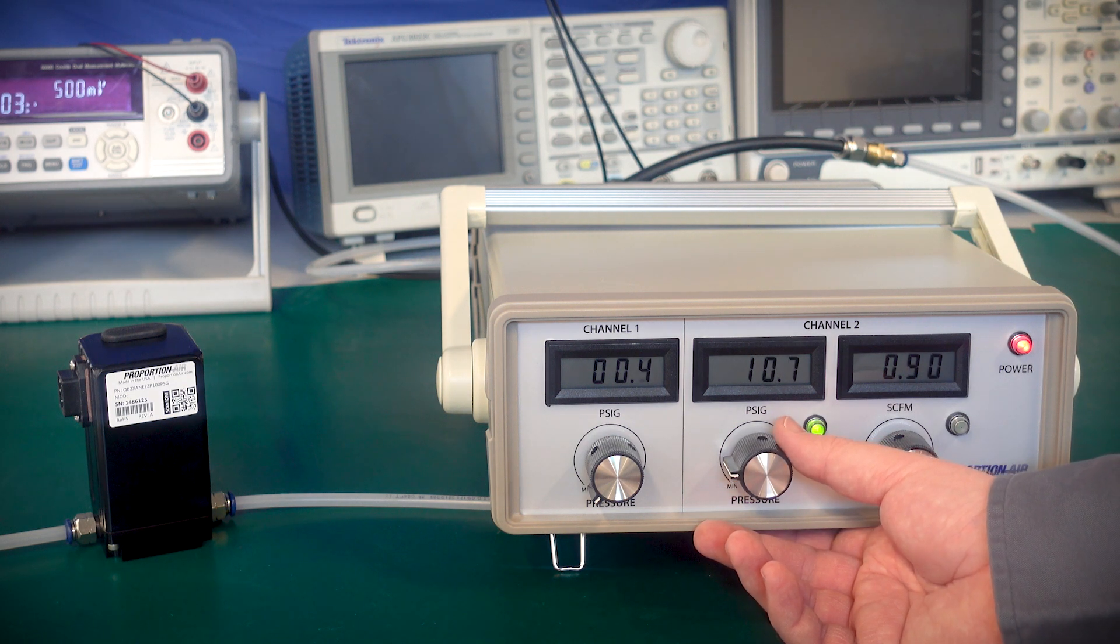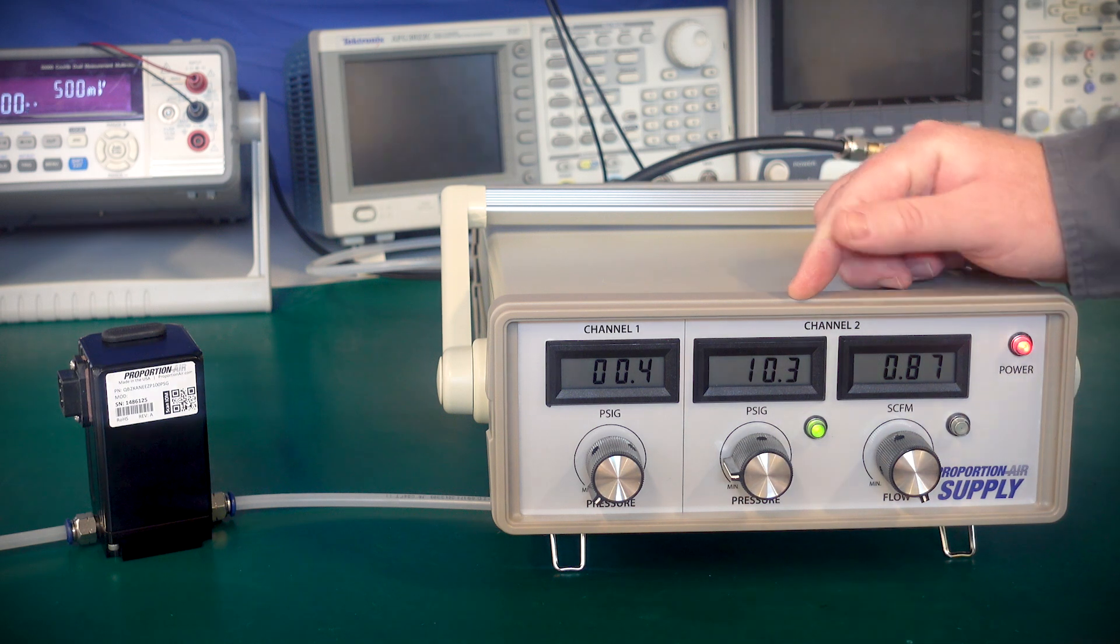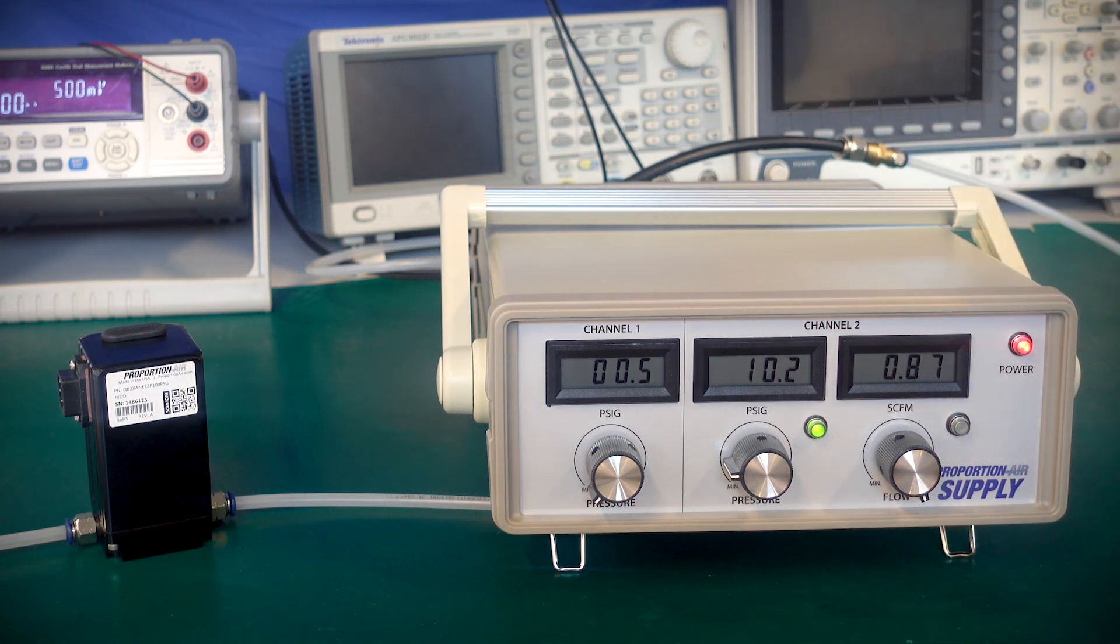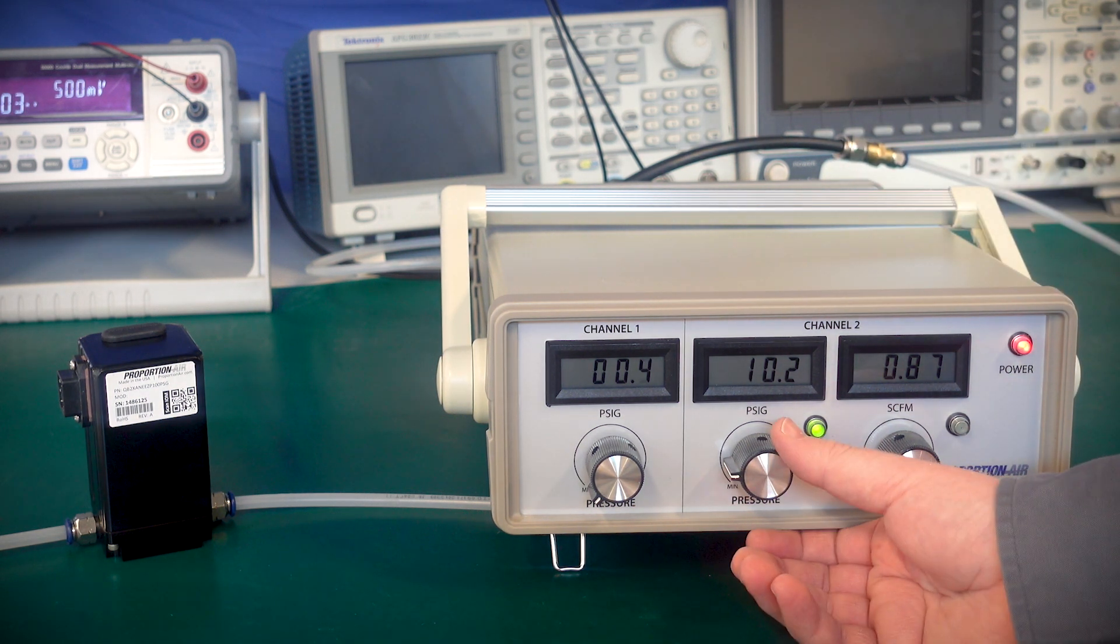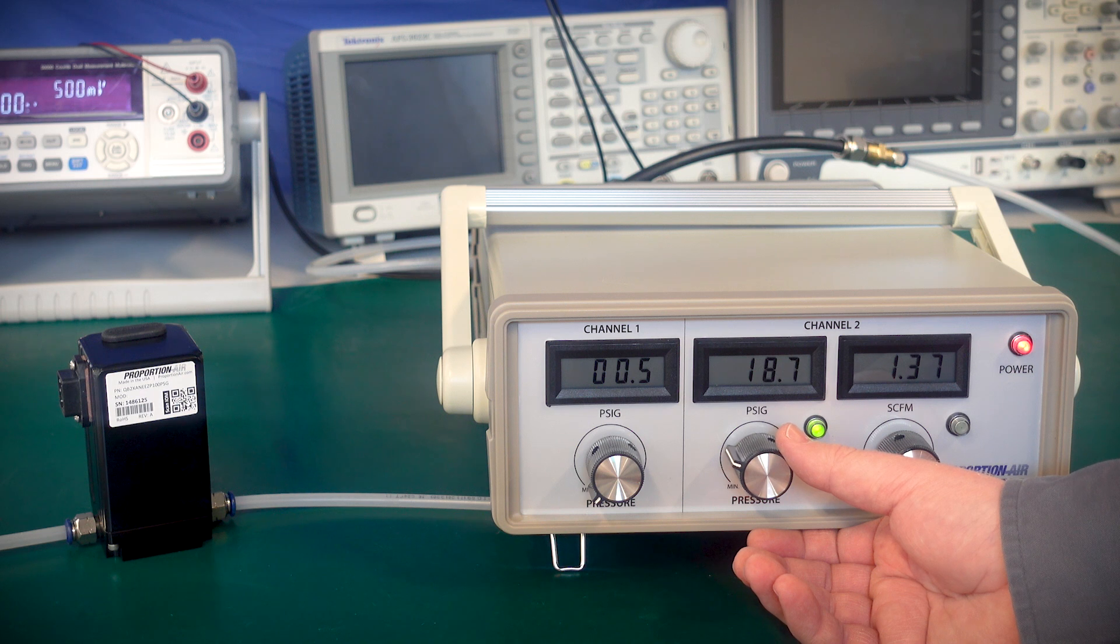To do so, we will turn the flow up to maximum so it is not limiting, and we will adjust the pressure. As we get to a set point, we will read the flow. We will adjust to the next set point and read the flow there. You can put these points on a graph and generate your flow curves.